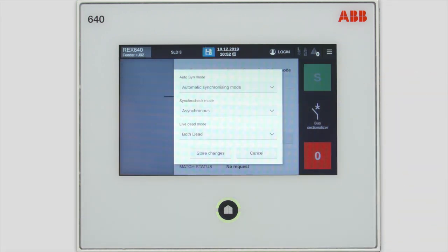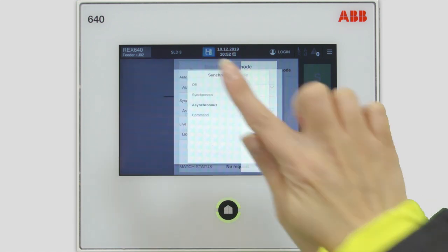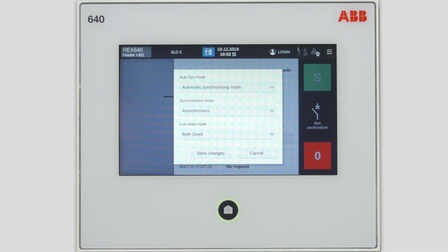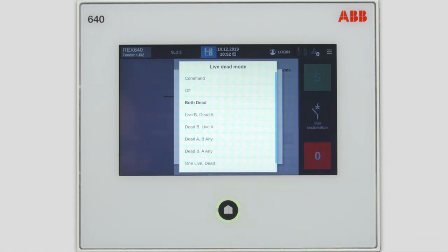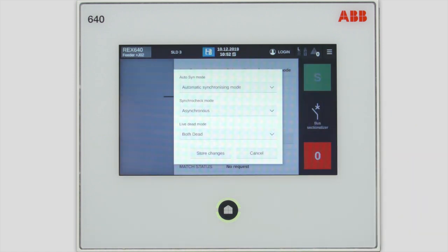In case the two network parts are already running in synchronous mode, meaning there is no need to actually control the generators on different sides of the bus bar, only SyncroCheck will be applied. There are different modes for the SyncroCheck functionality: asynchronous mode, meaning you use it when you want to adjust the selected generator, or synchronous mode, which is needed when the generators are already running in a synchronous manner. Let's stick with the asynchronous mode. Also, in cases when one side of the circuit breaker or both sides are dead, meaning not energized, you still have the possibility to close the breaker by selecting the relevant mode in the live/dead mode settings.